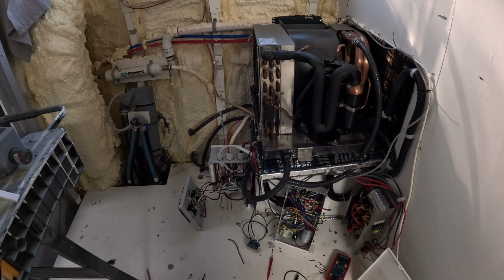When it needs the pump, it will have a 220 volt coil relay, and the 5K one has a 110 coil relay, but they both switch the 110 that goes to the pump through the 5 amp breaker. The 5 amp breaker goes there, then out to the pump, and the pump gets its ground and neutral from these 2 lines here, as does the 5K.